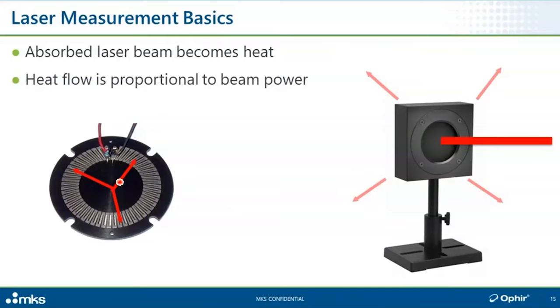This disc, we're looking at the inner surface of the disc, so you can actually see the thermopile ring in this case. The beam would be absorbed from the other side of this disc. There's an appropriate absorber there. The absorbed light turns into heat, which then spreads radially outward. We measure the heat flow. It's proportional to the power of the beam that came in. The constant of proportion, by the way, is what we measure when we calibrate the sensor. Then the heat generates an electrical signal that's proportional to the beam. The sensor is calibrated, so the instrument will then know how to convert that signal into a reading. The heat then had better go away, otherwise the temperature is going to build up and something unpleasant might end up happening to the sensor.